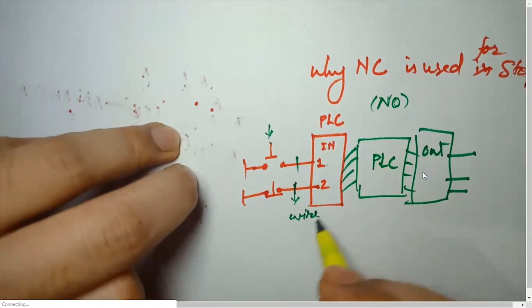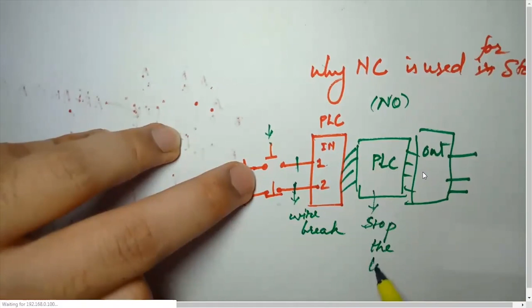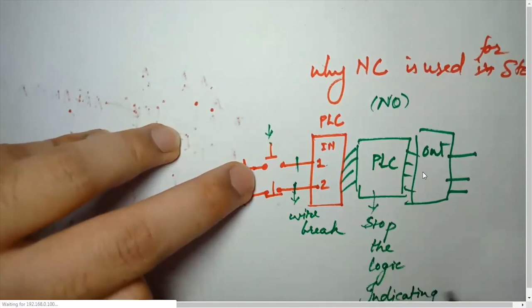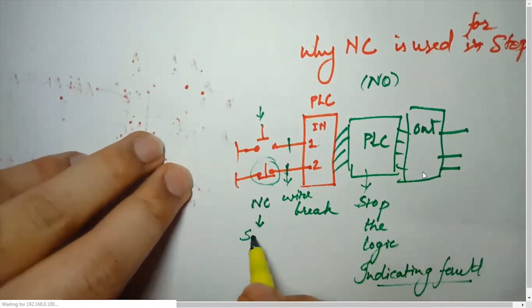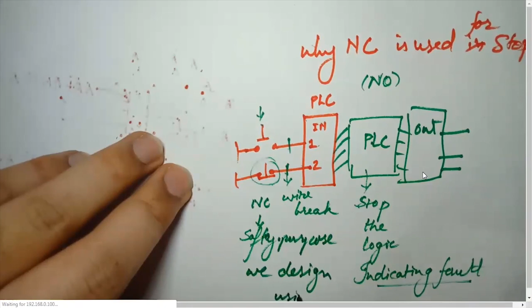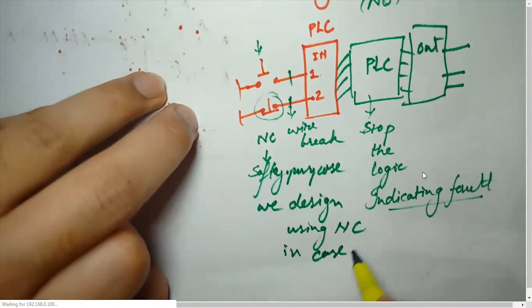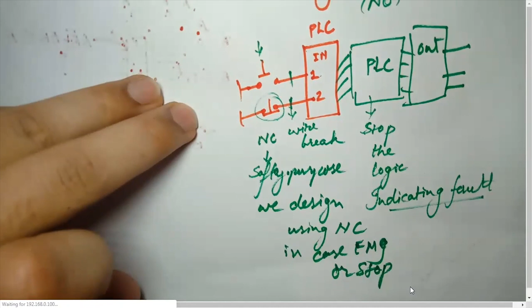In the NC case, if a wire break happens, the PLC will automatically stop the logic and indicate a fault. Both things are possible with this kind of button. So for safety purposes, we design using NC in case of emergency or stop. I hope you have got the answer why we are using it.